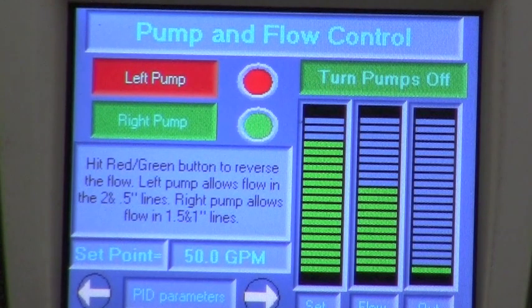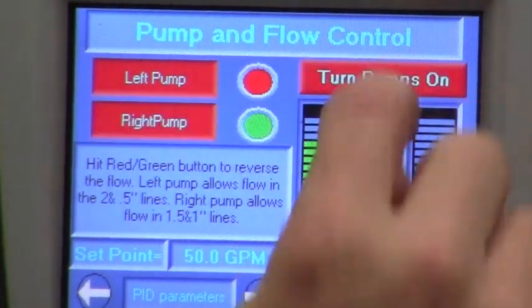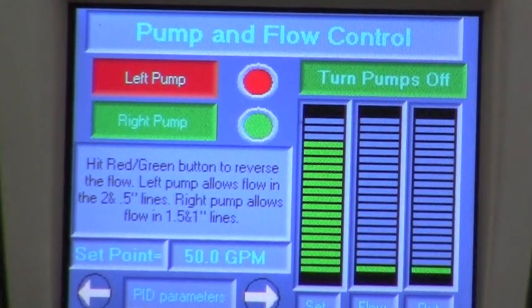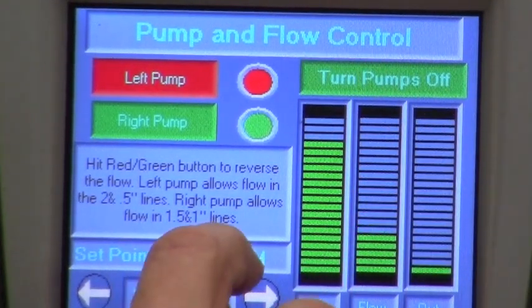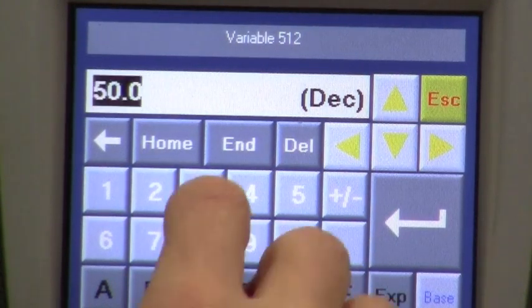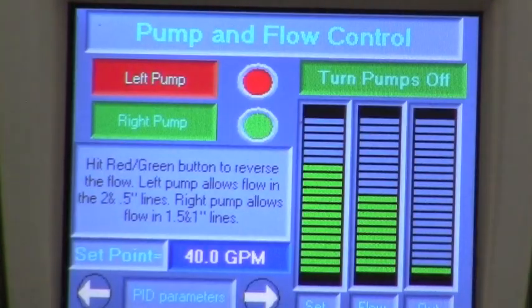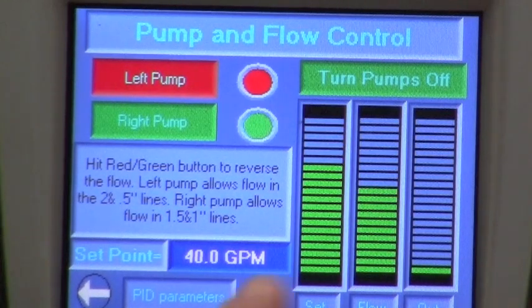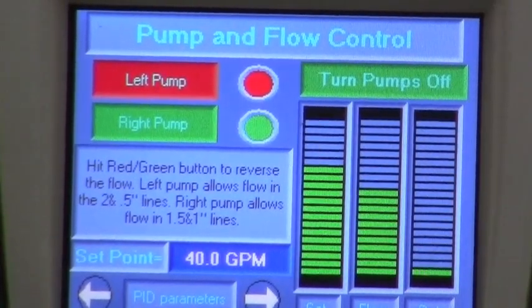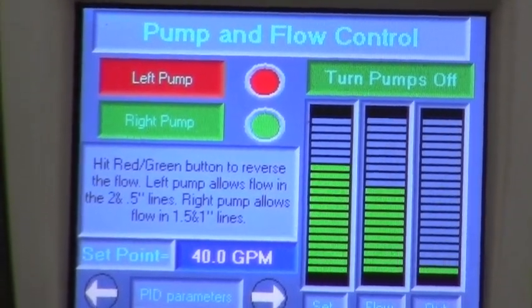And this is our control screen. Here, once again, it's a touch screen — I can turn the pumps off and turn them back on. Here's my set point for flow. I can go in here and you get the numeric keyboard. You can type in your set point and it changes. Just like a typical PID control, you have your set point, flow, and output. So we have full PID capability within this unit.